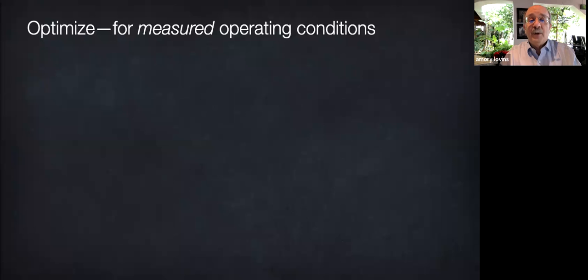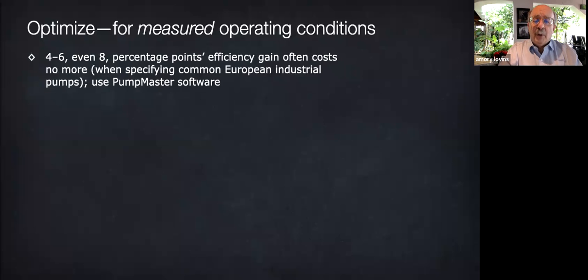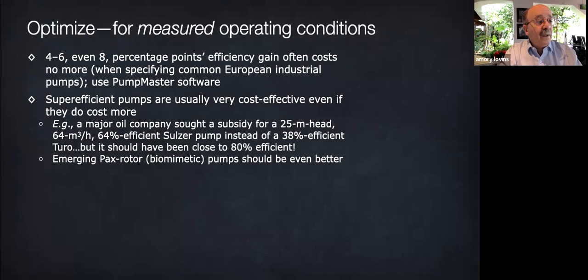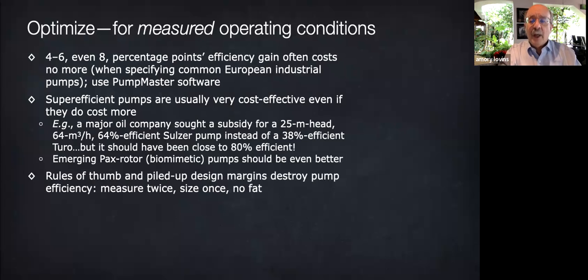Similarly for fans. If you shop carefully, far more efficient pumps and fans often don't actually cost more. But even if they did, it would usually be worthwhile. Also, you do need to specify the pressure head and the flow actually experienced by the pump once you've installed it, not just some rule of thumb. Most pumps are oversized by misapplying many successive design margins.